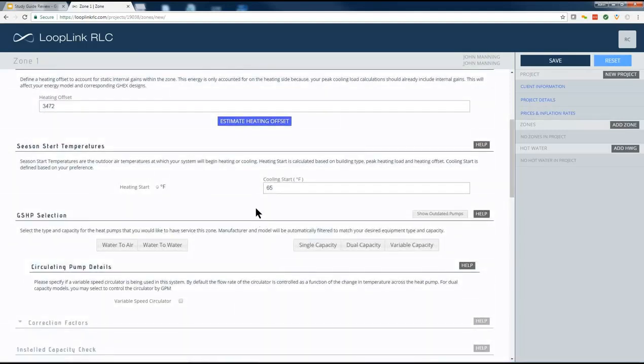So beyond that, next stage of the process is to go ahead and specify heating and cooling start temperatures. Heating start temperature is actually calculated based on the ratio of heating offset value to your peak heating load. So you don't have direct input over that, but the cooling start temperature you actually do.